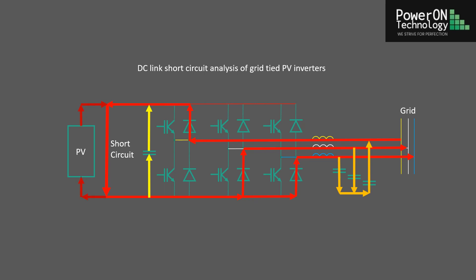The third and last component of the fault current is the current from the PV array itself. As shown in a previous video, this current can last several minutes before the PV fuse trips. Recent comments received indicate that there are some installations where the PV fuses are being omitted completely, which is not advisable. When the upstream fuses are removed, this PV fault current can flow indefinitely and cause severe damage.